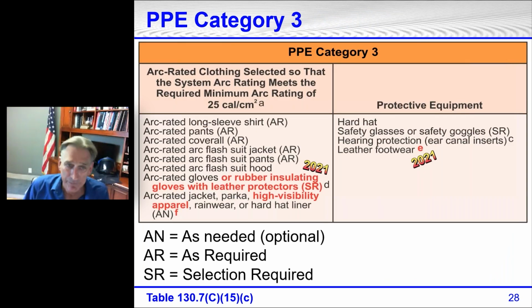PPE Category 3. Now the minimum arc rating for PPE Category 3 is 25 calories. And other information on there, AN stands for as needed, AR as required, SR would be selection required. There's a little bit of change. There's a footnote E now that wasn't there before, where it says leather footwear. In fact, it used to say heavy duty leather footwear, and the committee took out the words heavy duty. If you want to look at the footwear footnote, take a look at that after the webinar.